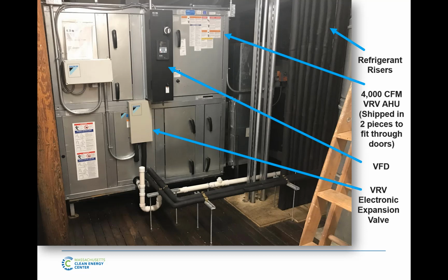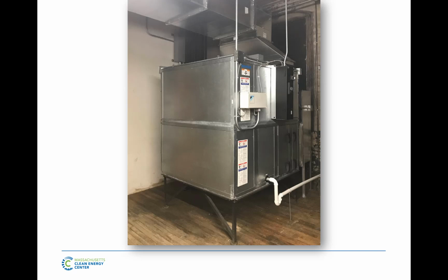So something to think about for retrofit work. If the idea of putting fan coils everywhere doesn't work, we can replace and reuse existing duct work here with this concept. Very cost effective. The alternative was they're going to do a water source heat pump. So big 10-ton water source heat pumps up to the roof. The problem is they could not have turned that on until everything was finished and the condenser water loop was finished. We were able to do this by doing 1 mechanical room at a time and only have 1 week of downtime per tenant and everything. So that was the big part of the project.